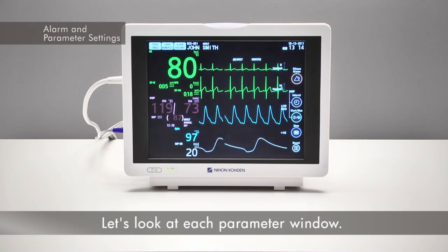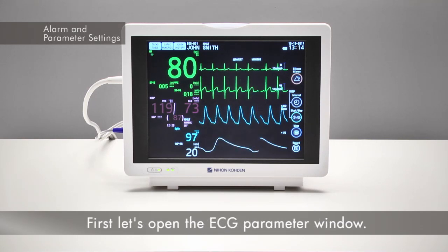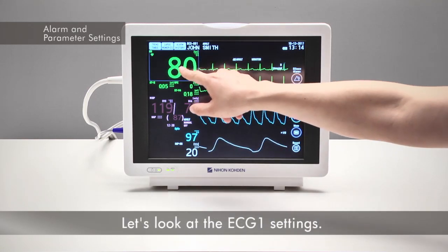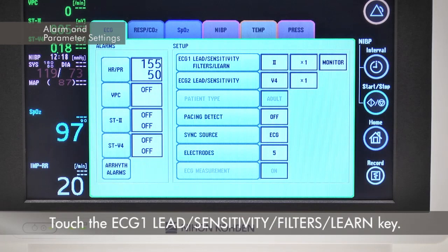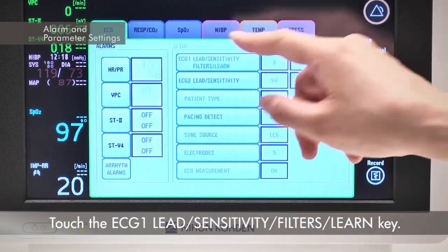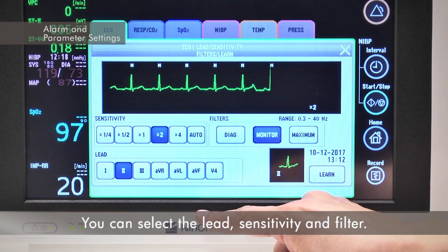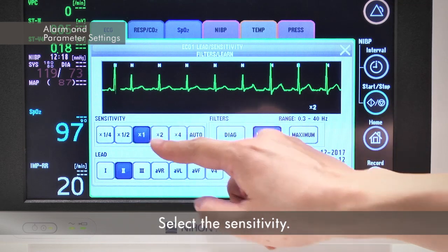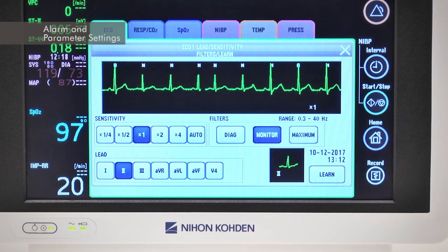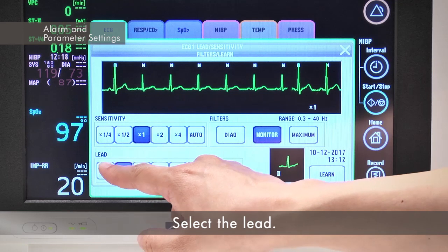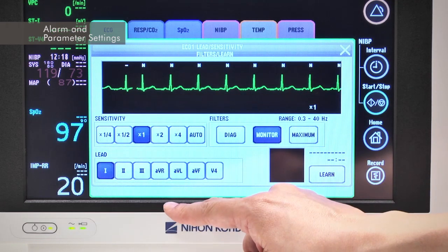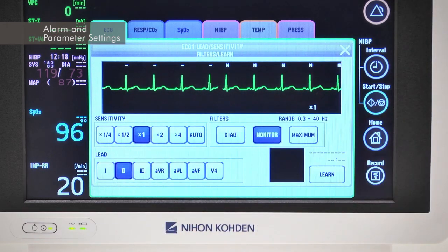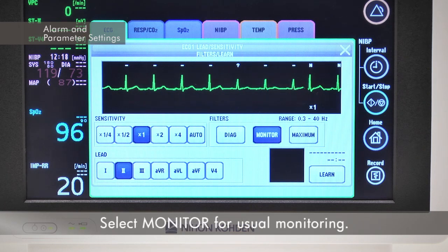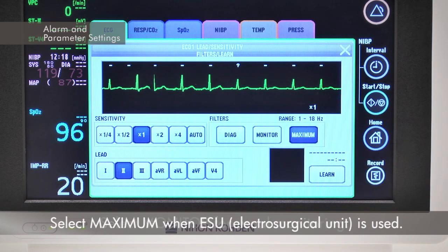Let's look at each parameter window. First, let's open the ECG parameter window. Let's look at the ECG1 settings. Touch the ECG1 Lead, Sensitivity, Filters, Learn key. You can select the lead, sensitivity, and filter. Select the sensitivity. Select the lead. Select the filter. Select Monitor for usual monitoring. Select Maximum when ESU is used.